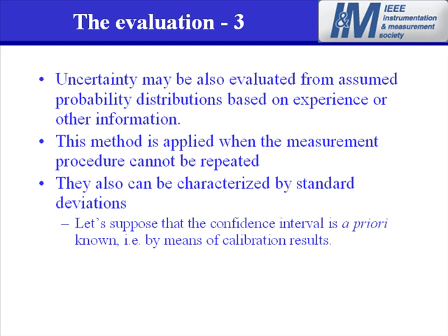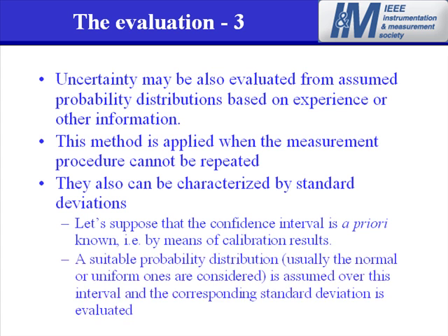In fact, let's suppose that the confidence interval is known a priori, for instance because it is provided by calibration results. In this case, we may assume a suitable probability distribution over this interval, and the most employed are the normal or the uniform distributions, and then evaluate the corresponding standard deviation.